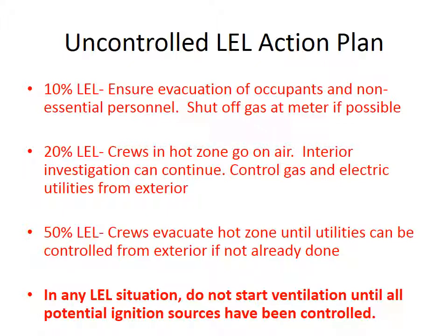In any situation where we have a lower explosive limit or LEL reading, we want to avoid starting ignition or ventilation until potential ignition sources have been controlled. So gas shut off, power shut off. And that comes from, again, that NIOSH report. You have that situation where you have gas buildup in void spaces. It's potentially over the UEL, or too rich to burn. What you want to avoid is just starting that ventilation blindly until you have those ignition sources controlled as best as possible.